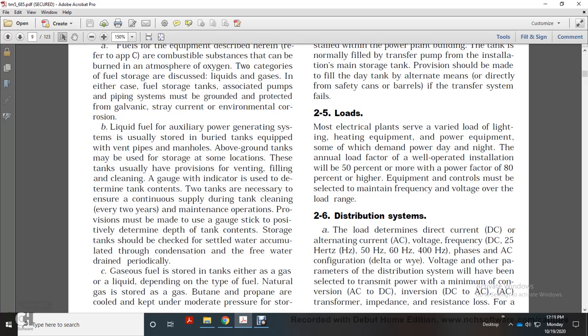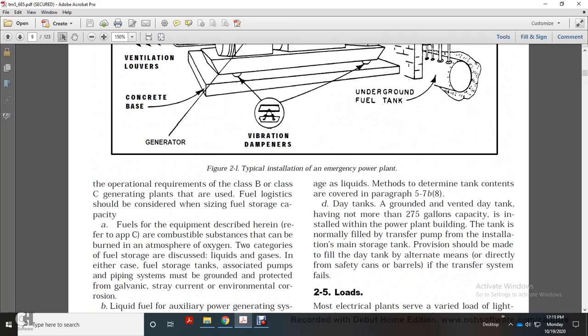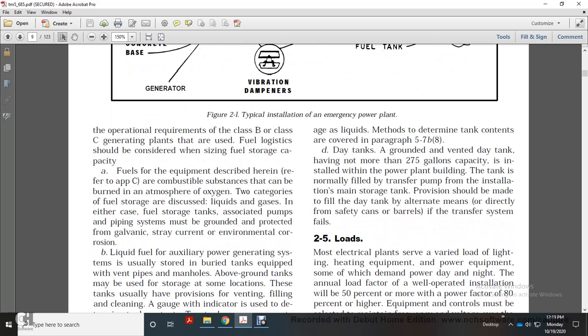Storage tanks should be checked for settled water accumulation and condensation; free water should be drained periodically. Gaseous fuel is stored in tanks either as gas or liquid, depending on the type of fuel. Natural gases such as butane and propane are cooled and kept under moderate pressure for storage. Day tanks of no more than 275 gallons may be installed within a power plant building. The tank is normally filled by a transfer pump, but provision should be made for filling the day tank by alternate means directly from safety cans if the transfer system fails.